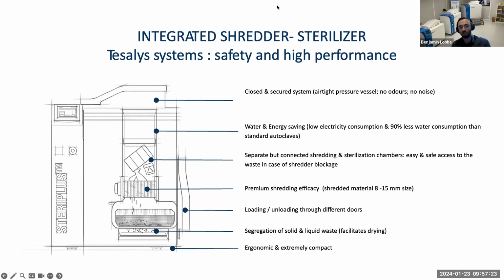And then we will start the sterilization cycle. We are an autoclave, so we will inject steam. There is a steam generator inside the unit that will reach 135 degrees for 10 minutes to sterilize the waste, of course, but also the full unit. So the loading chamber and the shredder as well will be fully sterilized, in order to ensure that it is very safe, and then we can perform any maintenance or load another cycle without any issue.